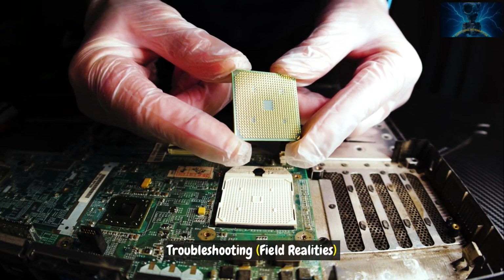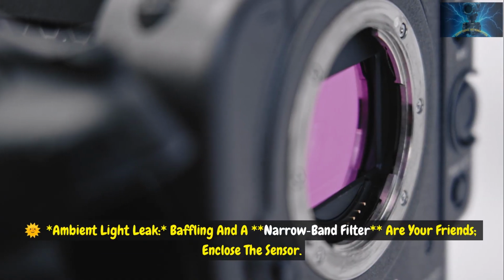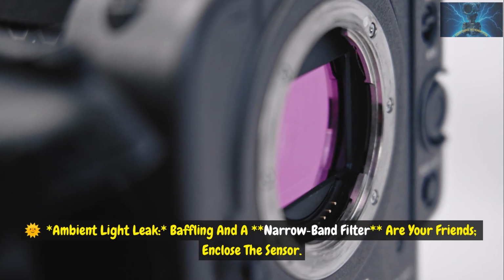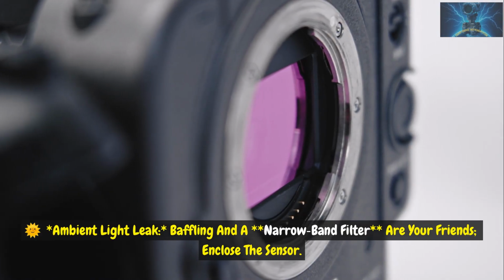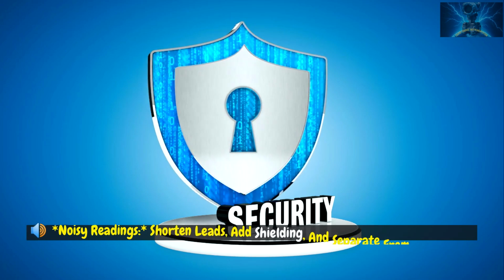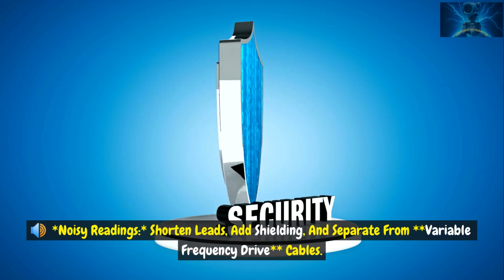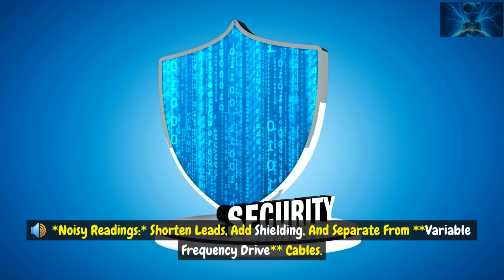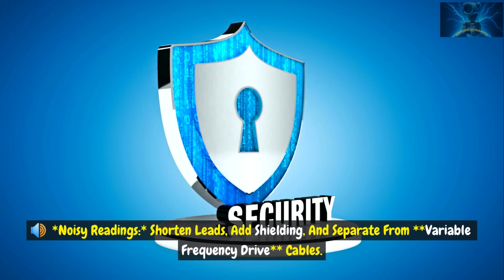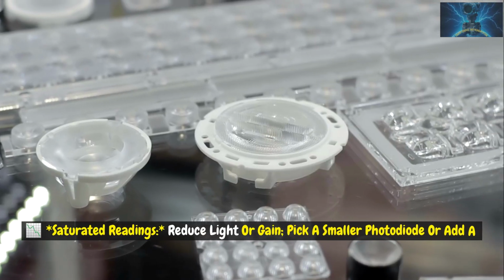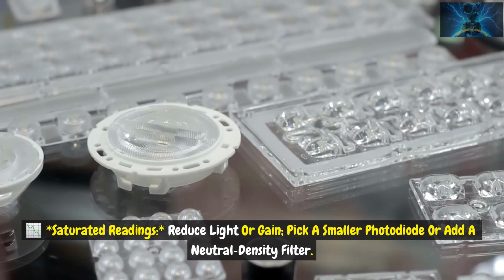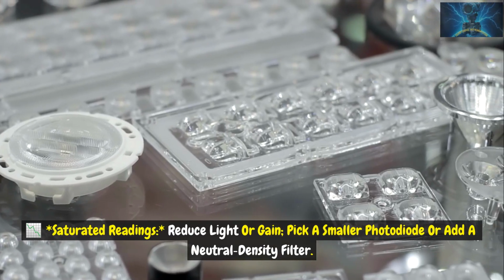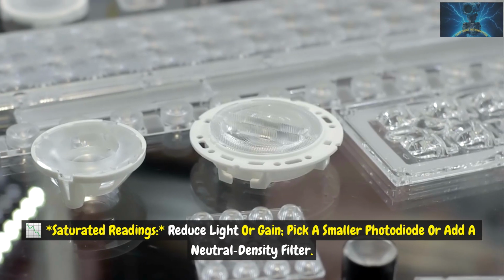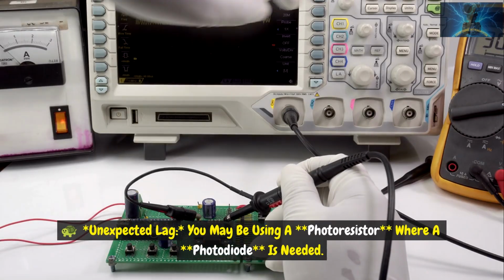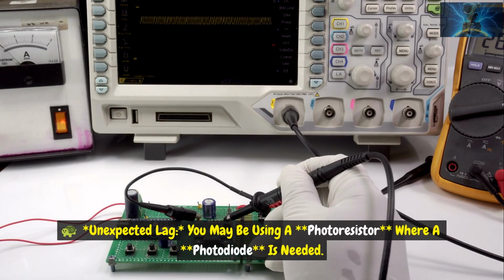Troubleshooting field realities. Ambient light leak: baffling and a narrowband filter are your friends, enclose the sensor. Noisy readings: shorten leads, add shielding, and separate from variable frequency drive cables. Saturated readings: reduce light or gain, pick a smaller photodiode, or add a neutral density filter. Unexpected lag: you may be using a photoresistor where a photodiode is needed.